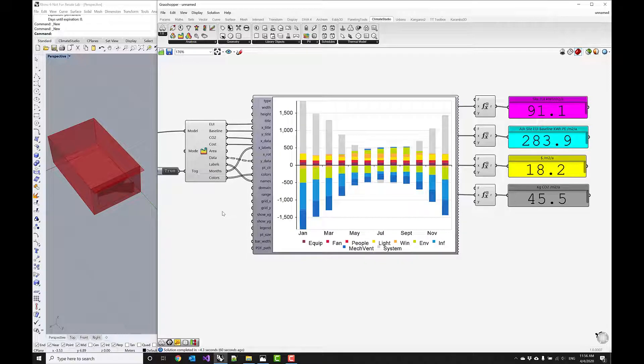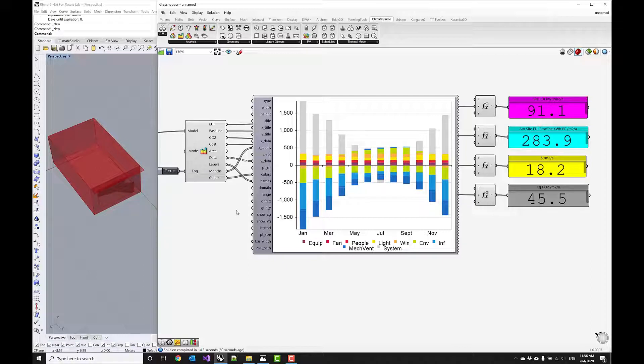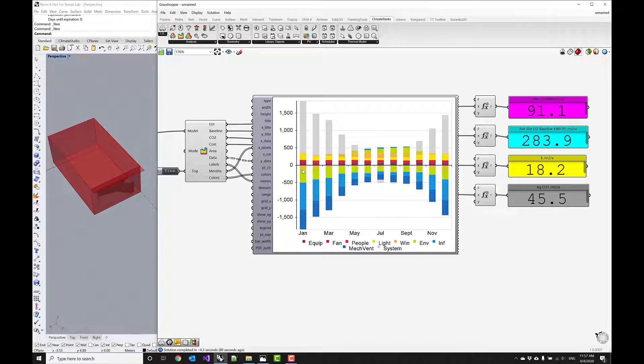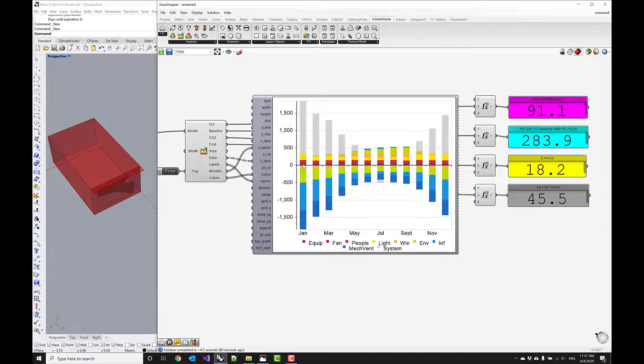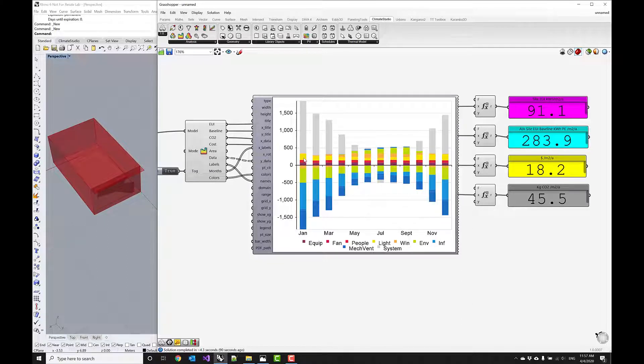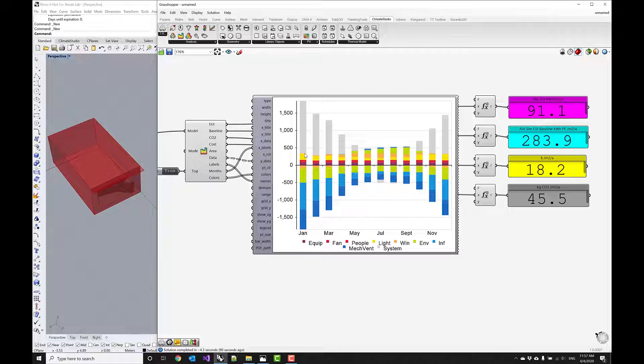Or you can also look at the energy balance that gives you a hint of where the energy and how the energy flows in the buildings. You see here the biggest most significant losses in the zone come from mechanical ventilation as well as infiltration. And then there's heat loss through the envelope right here and then heat loss through the window.